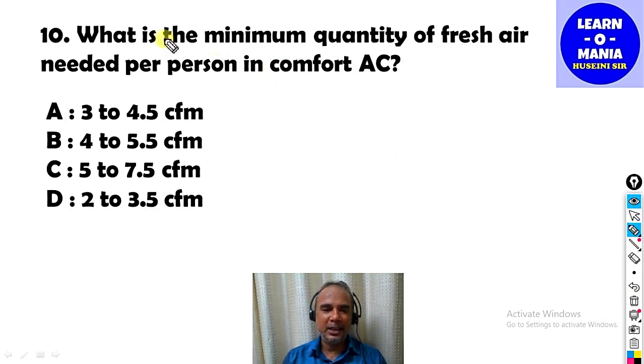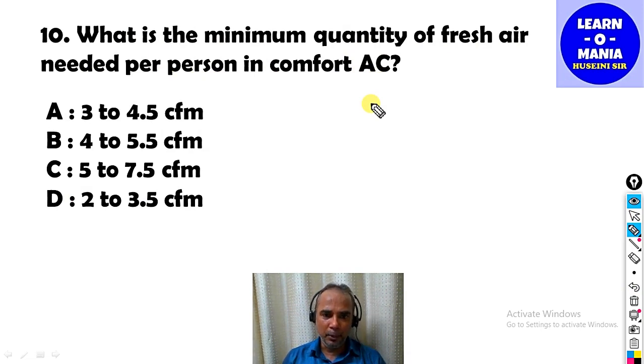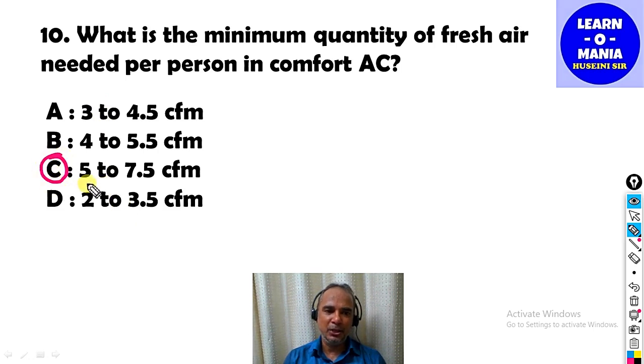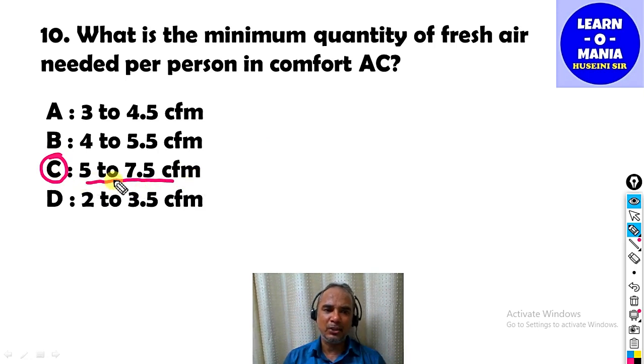Our next MCQ: What is the minimum quantity of fresh air needed per person in comfort air conditioning? The correct option is C — per person, 5 to 7.5 CFM (cubic feet per minute) of fresh air is required.